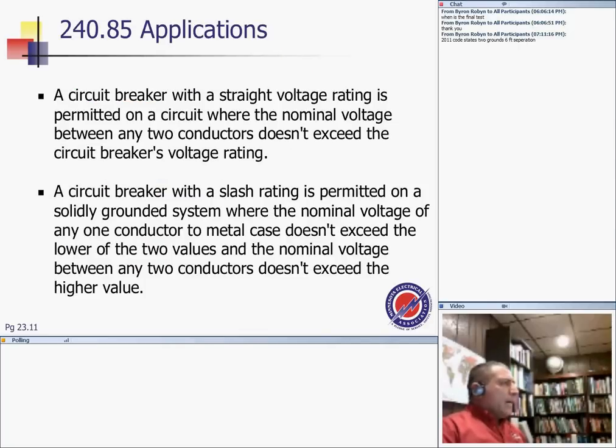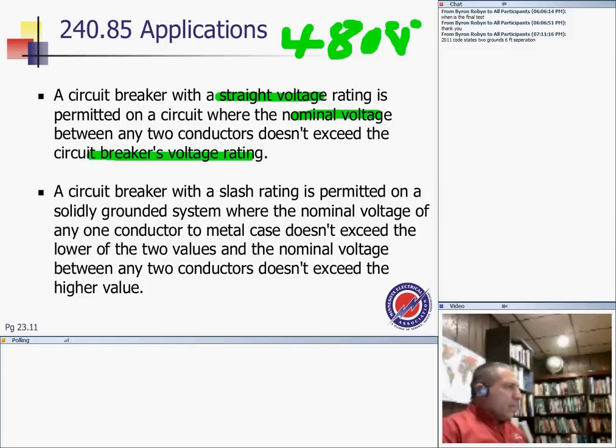A circuit breaker with a straight voltage rating is permitted where the nominal voltage between any two conductors does not exceed the circuit breaker voltage. So if I have a circuit breaker that says 480, I can't install that circuit breaker on a system that's higher than 480. A circuit breaker with a slash rating is permitted on a solidly grounded system where the nominal voltage of any conductor to ground does not exceed the lower of the two values, and the voltage between any two conductors does not exceed the higher value.